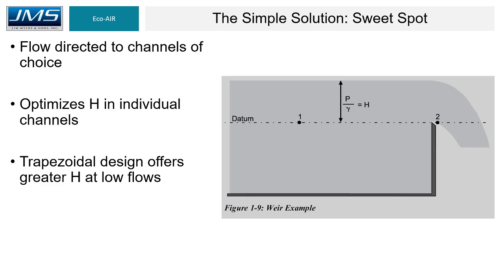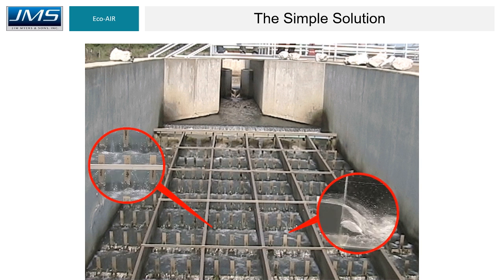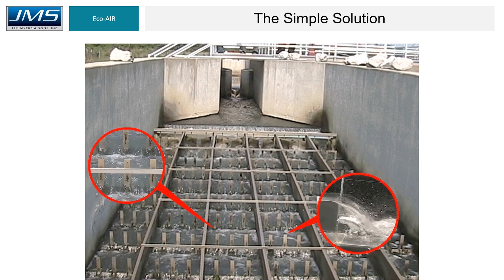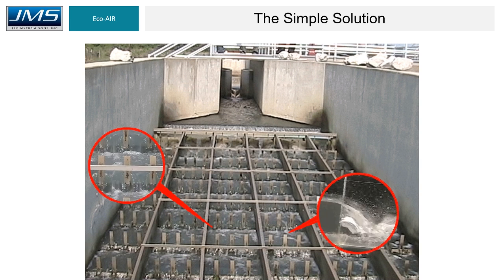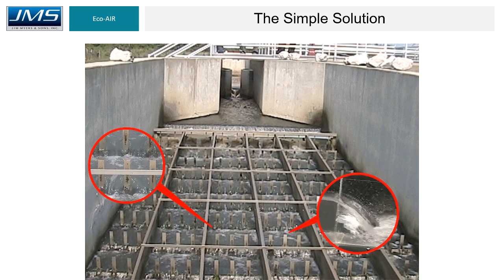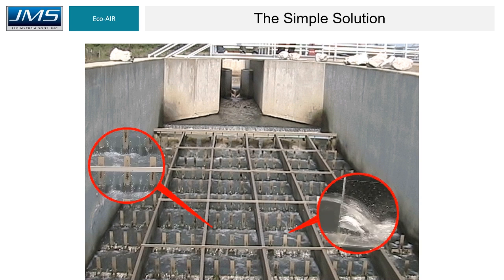H is the water level on each finger weir. As flow is directed to channels of choice via the influent flow control gate, H is optimized in each channel between two and five inches at the respective flow rate. The trapezoidal design offers a greater H at lower flow rates. In just two feet of fall with a floor slope of just four and a half to five and a half degrees, the LPCA accomplishes what in nature would be a waterfall.